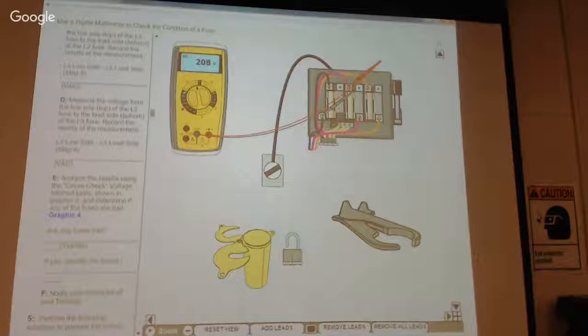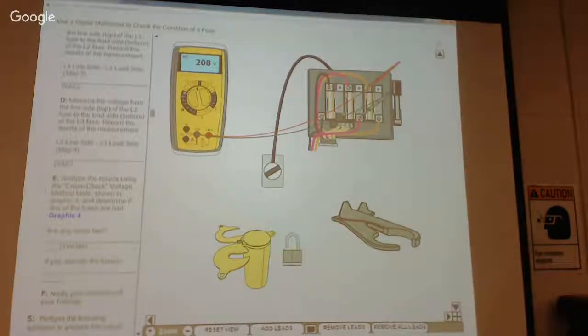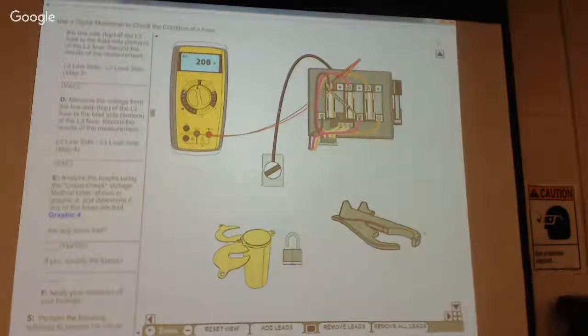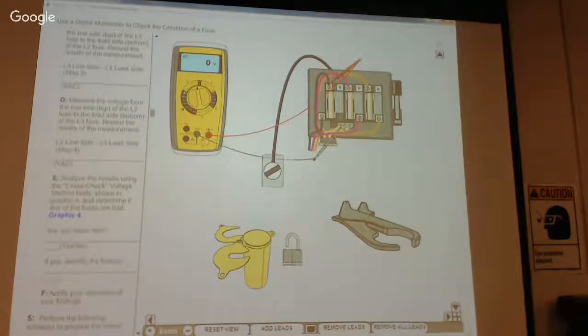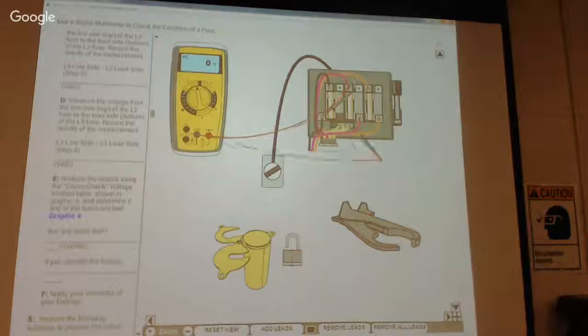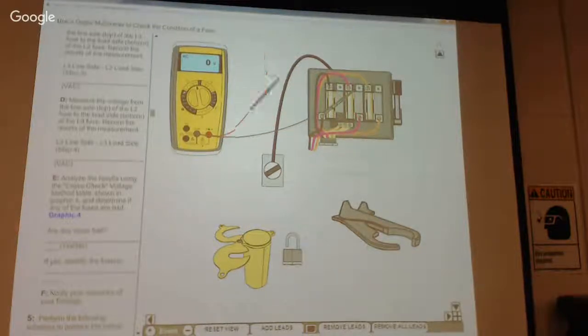That's right. And so what they're trying to do is, we know there's no fuse over here. And if we check to this one, we're reading 220 or 208. And then we're going to move down over here and check to here. We're reading 220. If we check to ground, it won't let me go to ground. But if we check to ground, we should be reading 120 volts on each one of these legs. Let me do that. So it goes through there and talks about doing a cross check to determine if all the fuses are good.